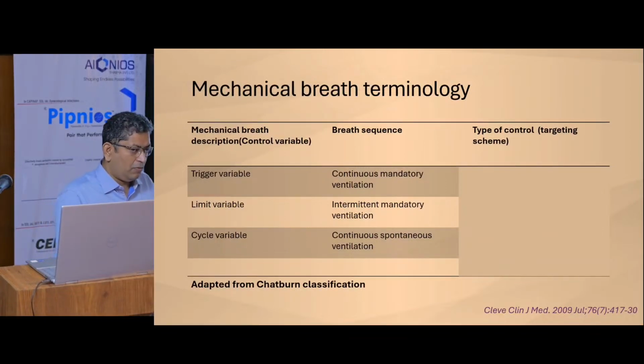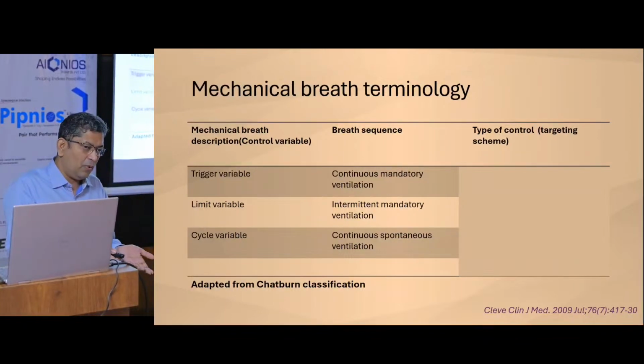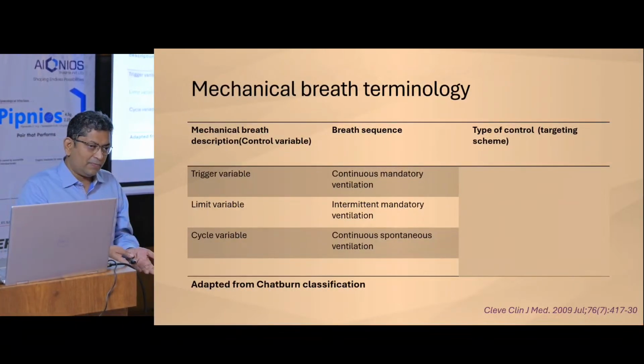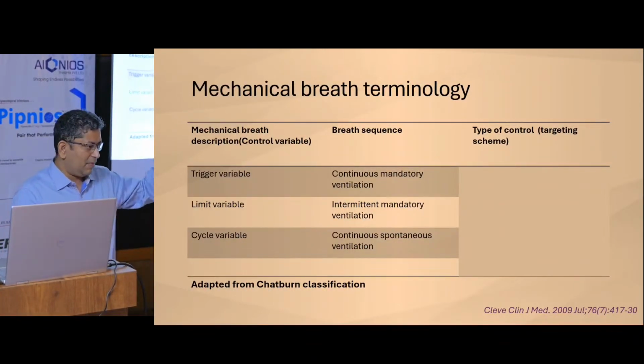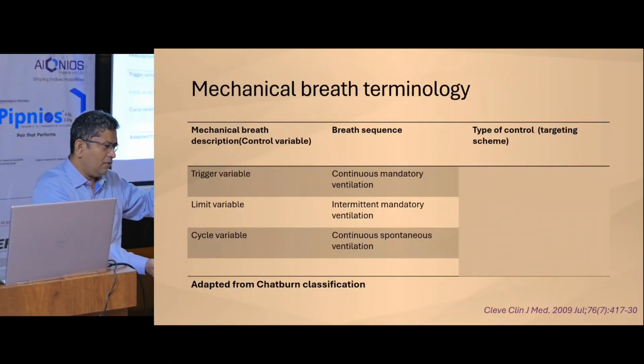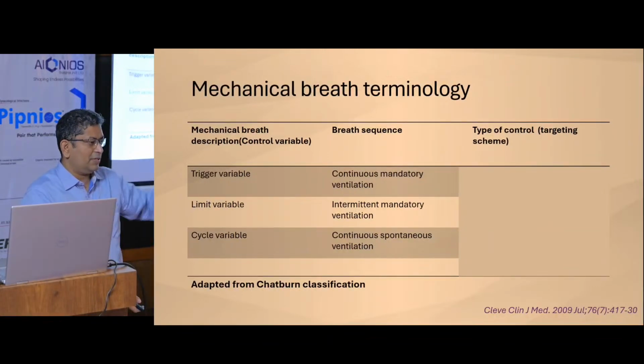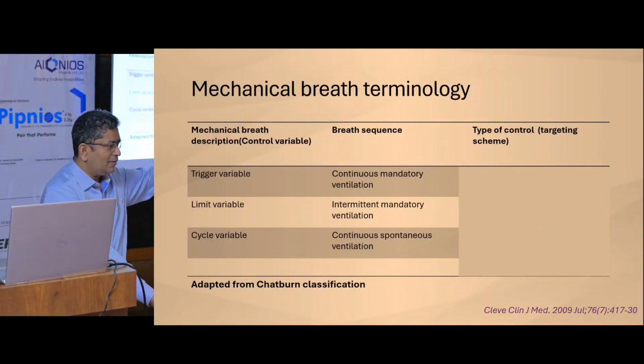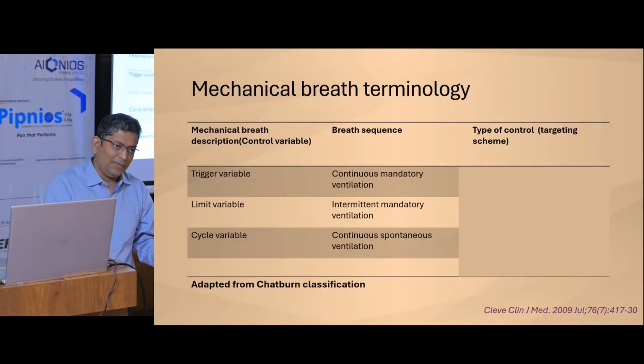How does the flow come? In a pressure control or a pressure support, when the ventilator triggers, the pressure suddenly goes up in the inspiratory limb. The pressure inside the chest is low at the peak, say 5. And then you suddenly put 15 pressure support. So pressure inside the ventilator goes to 20. And the pressure inside the chest is 5. So the air goes from the ventilator to the patient. That's how it goes. Right?